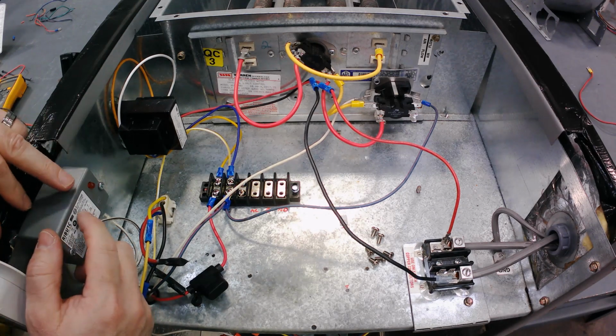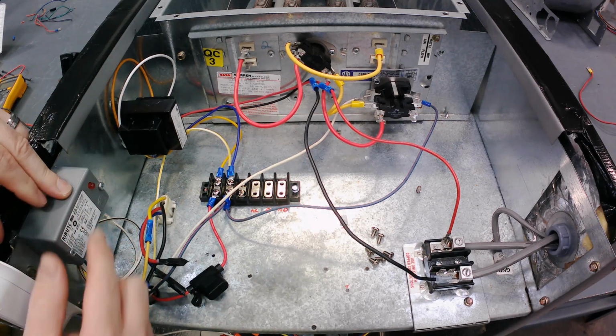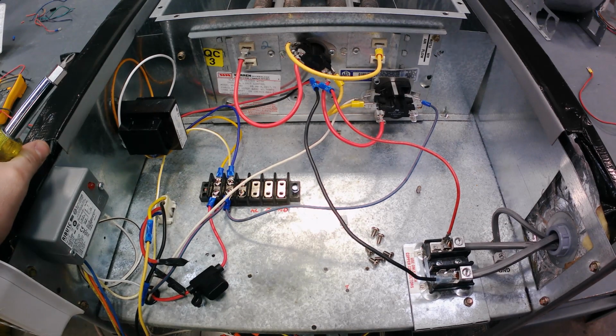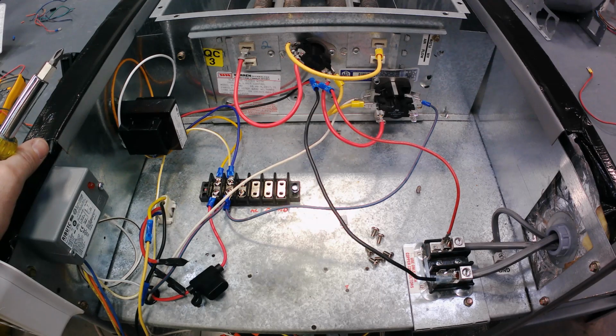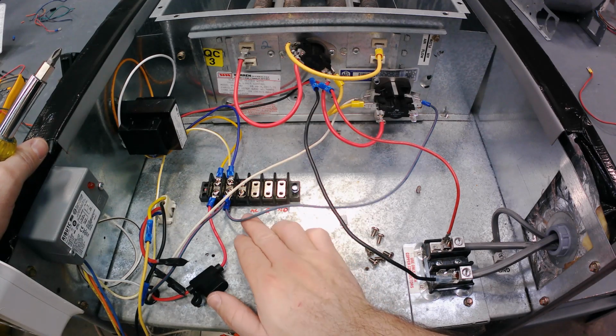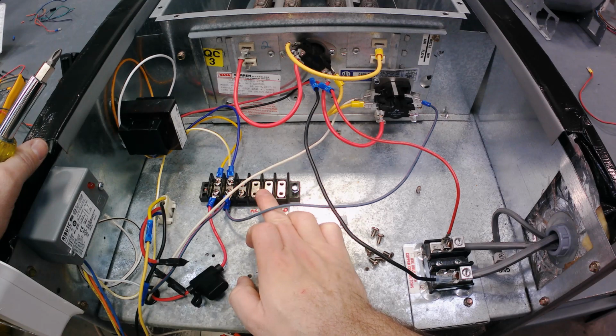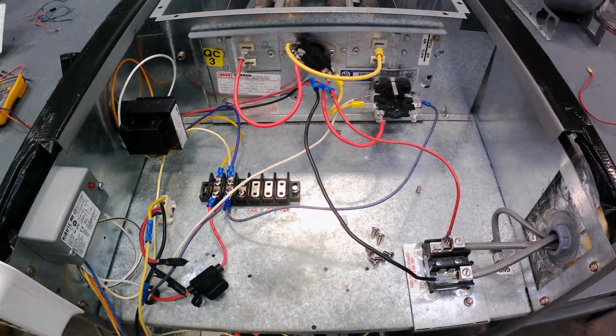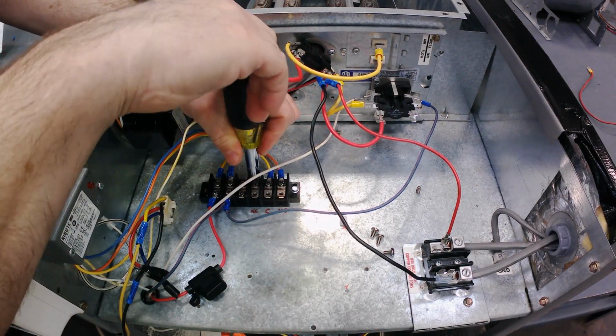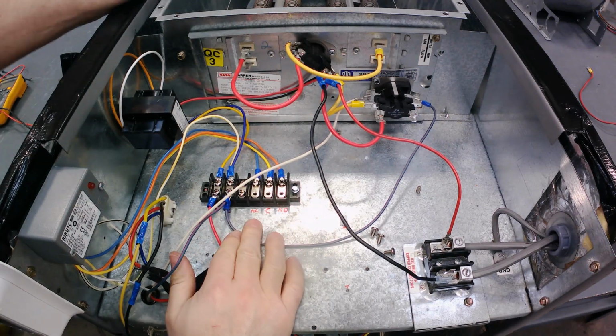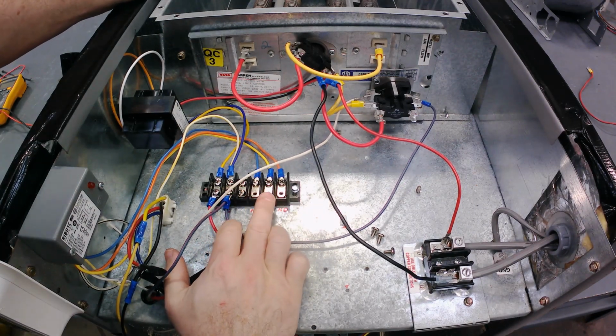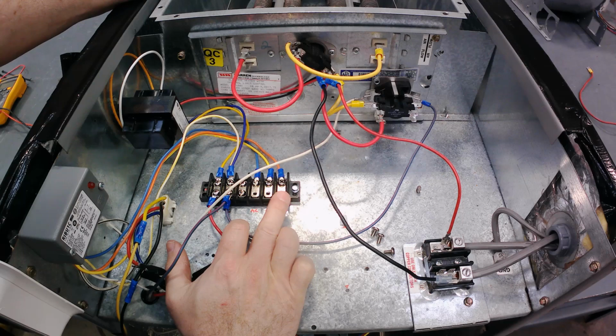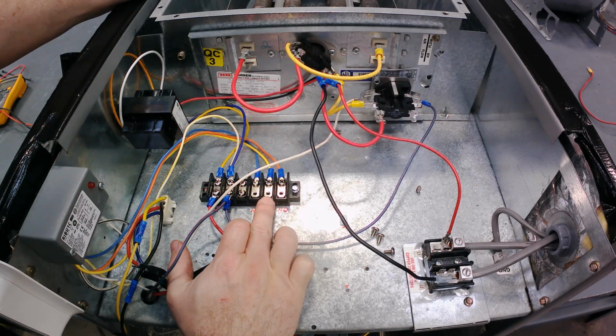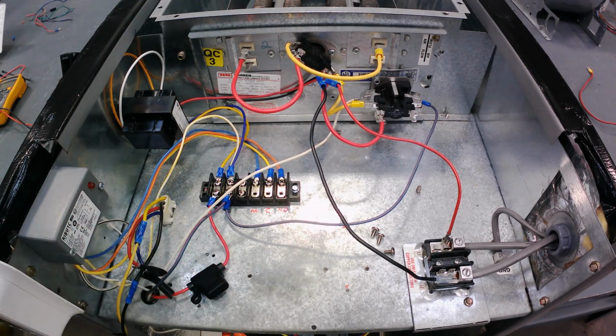So if you look at the actual RIB relay, it will tell you that the blue is normally closed, the yellow is common, and orange is your normally open. So we're going to wire blue, yellow, and orange on the back side. Alright, so we got all those there, and now on this side, this will be basically your connections to power and your motor and then your heat strip.